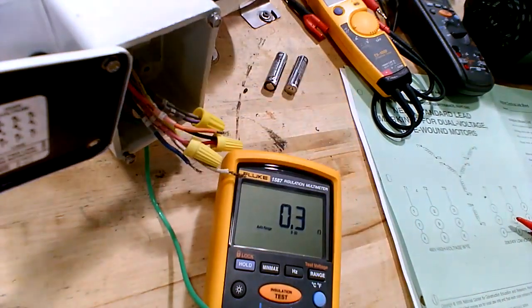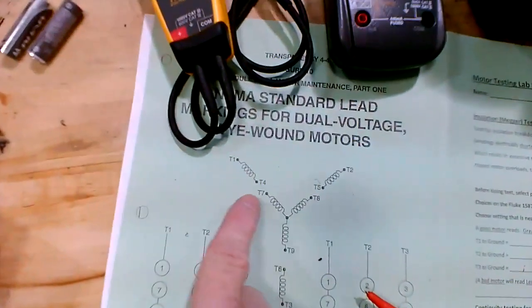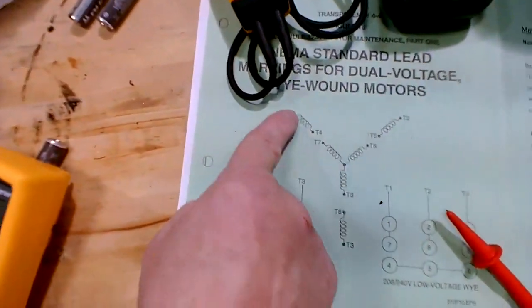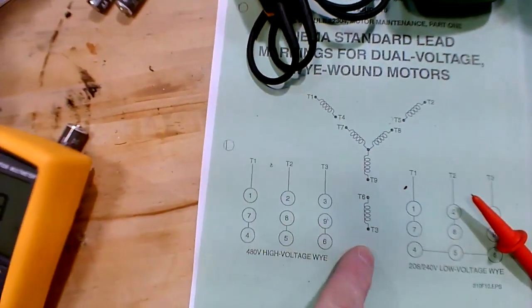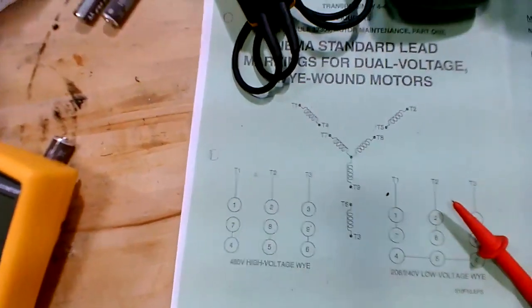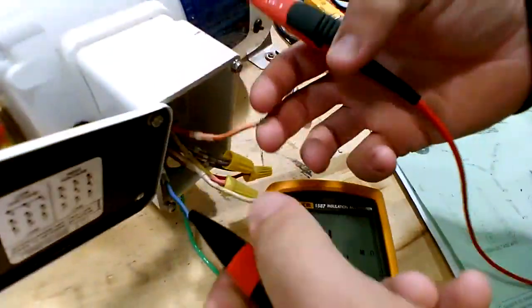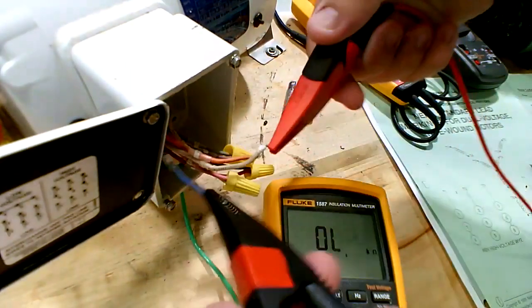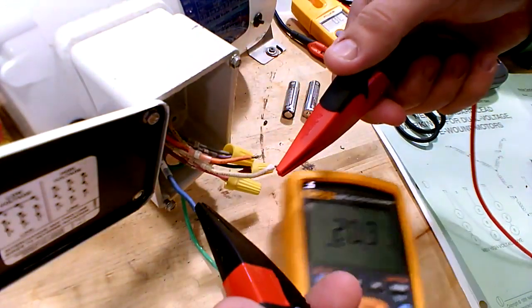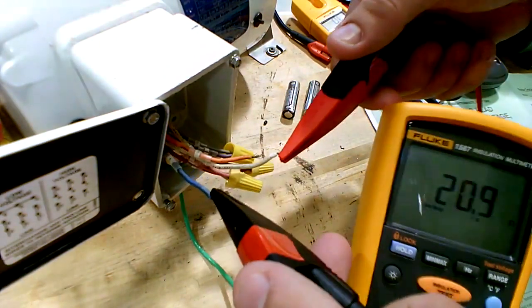Now he's going to check resistance through the winding. He's going to check it through the motor, 1 to 2, 2 to 3, and then 1 to 3, checking the continuity through them. 4 windings in series in each situation. He's finding out, do you have continuity or do you have a broken winding inside the motor? And in this case, you're going to be experiencing a balanced resistance reading in all 3 cases.